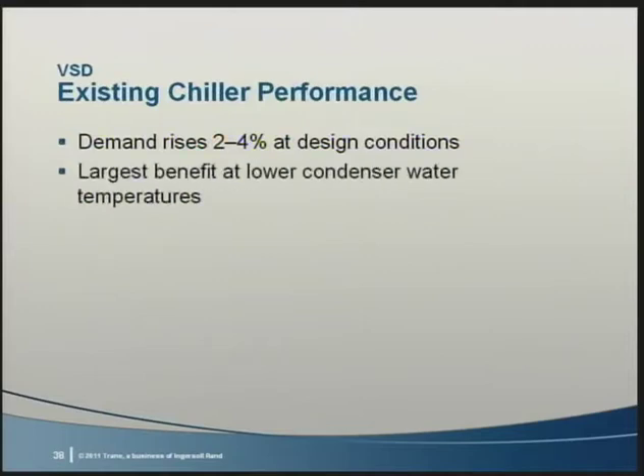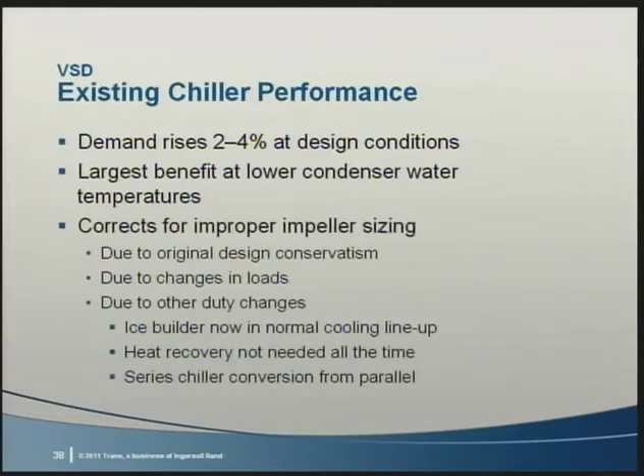Since the benefit of a variable speed drive occurs primarily when lower condenser water temperatures are available, we need to validate these conditions will exist enough hours of the year to provide a desirable return on investment. As Susanna pointed out, over the life of a building, it is not uncommon for a chiller to become improperly sized due to duty changes. The VSD can correct for this, providing the right tonnage at the lowest energy cost.